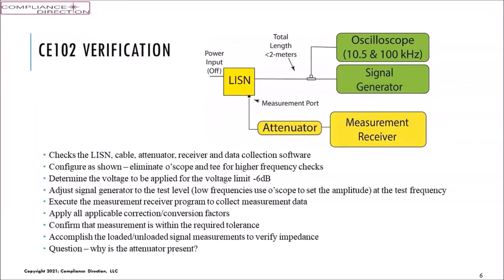And then we need to do a second piece. This was added for 461G because we weren't checking the impedance of the LISN. The LISN impedance at 10.5 kilohertz is approximately 5 ohms or so. The signal generator output is a 50 ohm source, so when we attach it to a 5 ohm load, it loads the circuit down. It loads the output of the signal generator. So even though it says we're outputting some voltage, what we're actually outputting is reduced significantly because of the loading effects. So the oscilloscope is used to measure what the voltage really is.